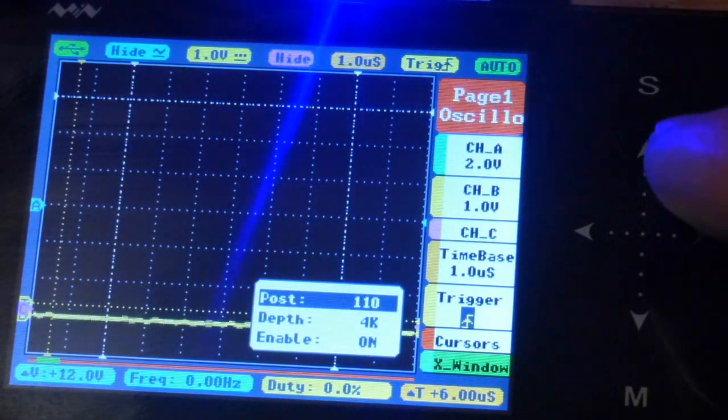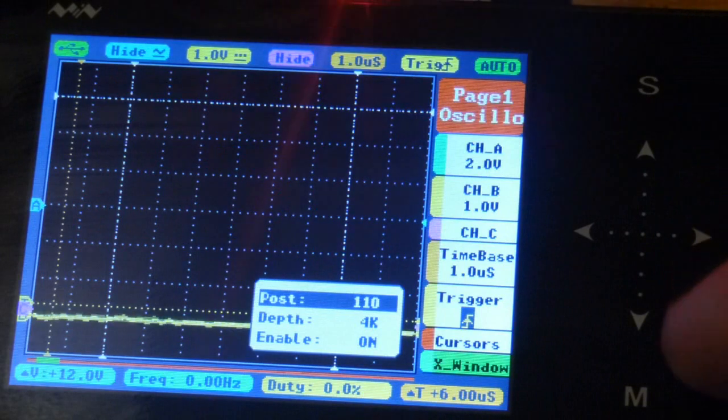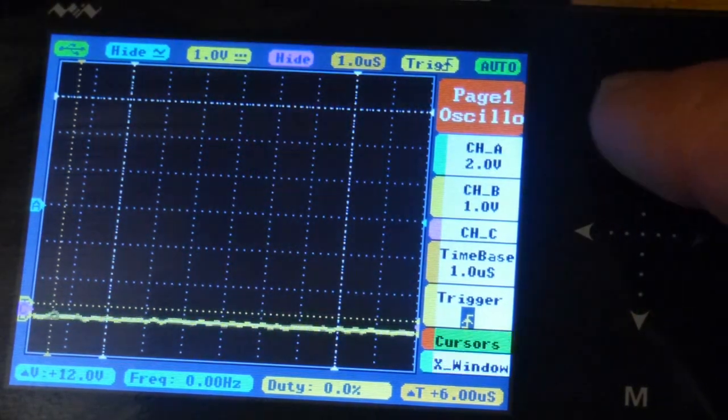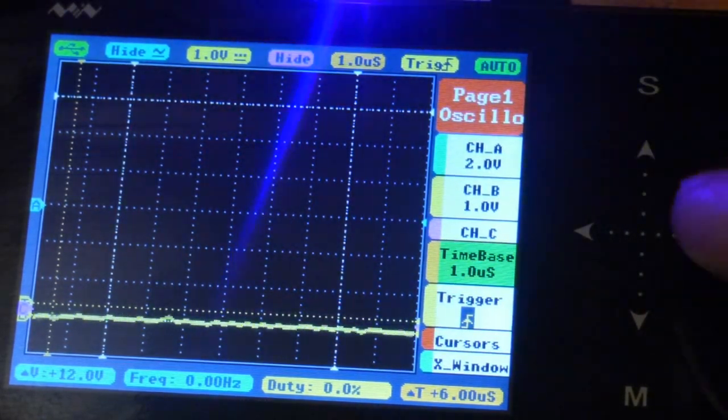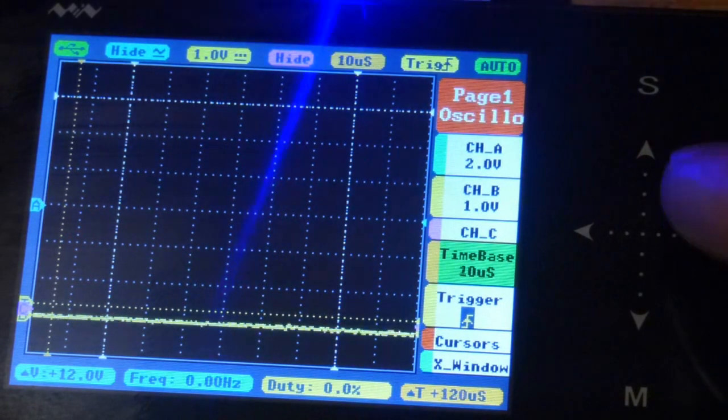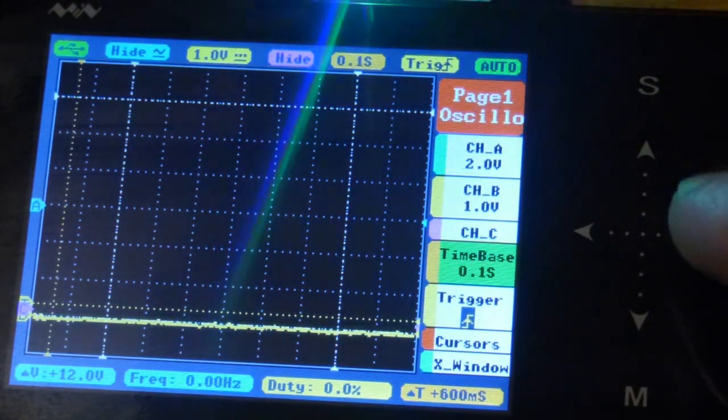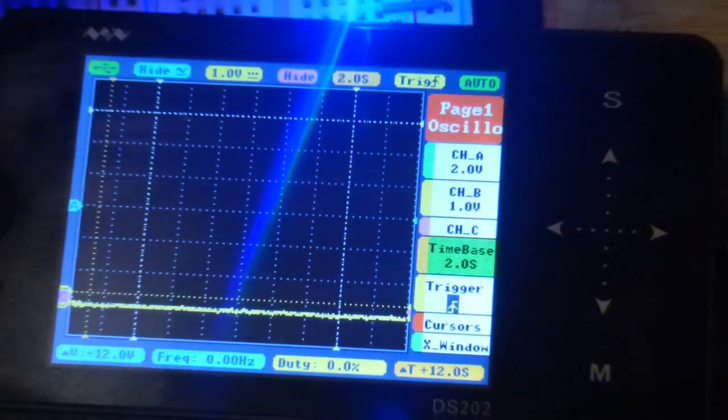That's the settings, the main settings - not too terribly complicated once you get a feel for it. So let's actually take the measurement. First thing I'm going to do is put the time base up to two seconds so that it moves slowly across the screen.